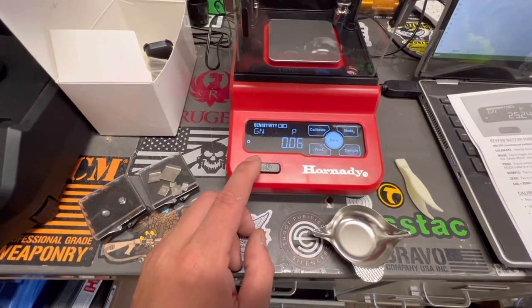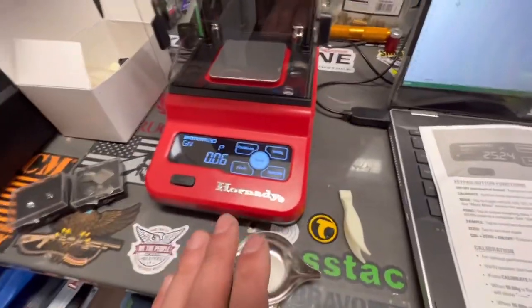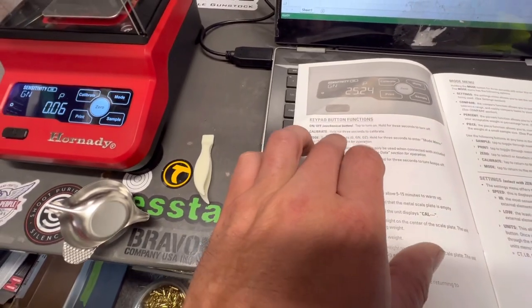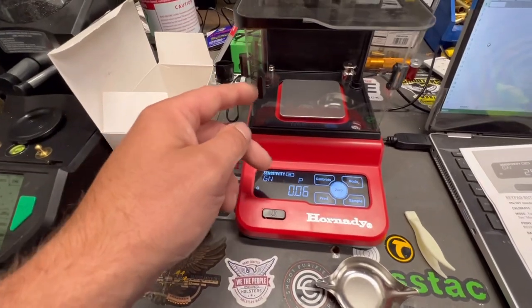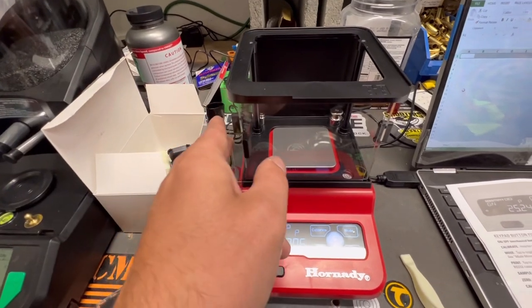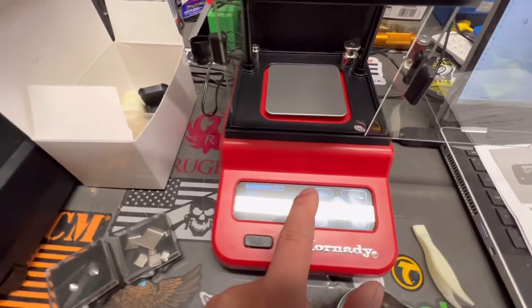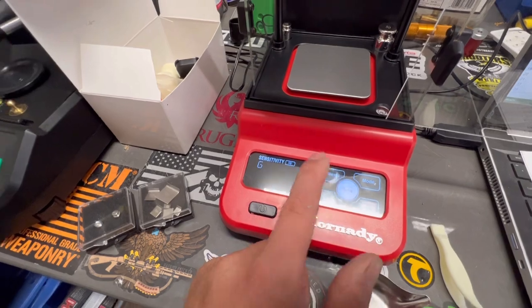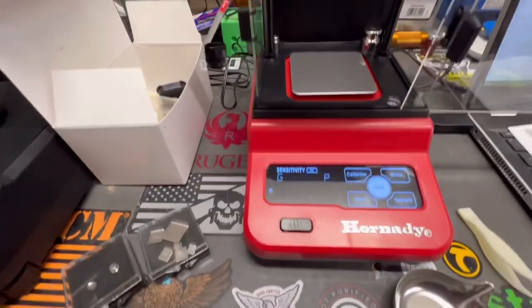I've already got the scale on — it's been warming up for about 20 minutes. To calibrate, the manual tells you to hold for three seconds. We're going to remove the windscreen and push it to the side, then hold the button for three seconds: one, two, three.